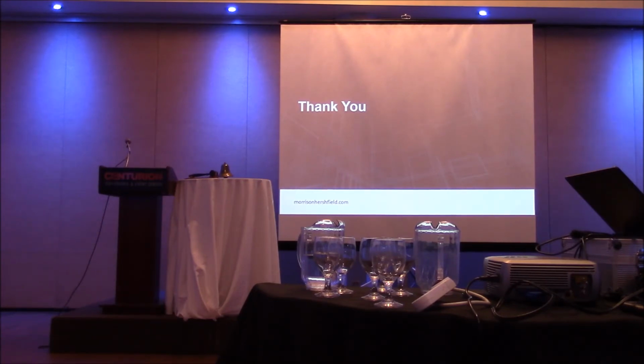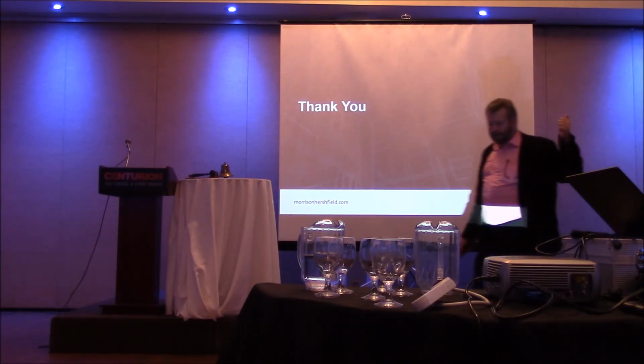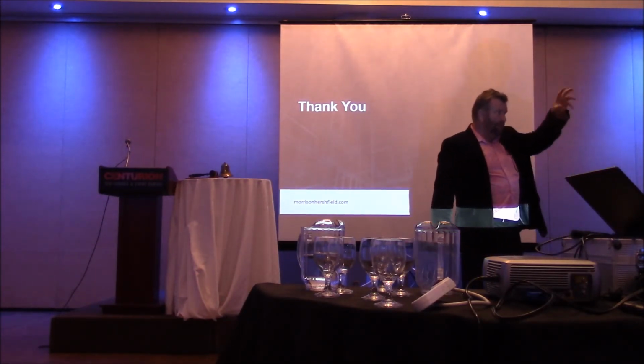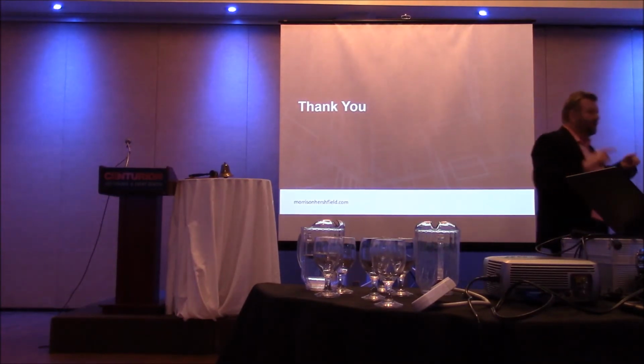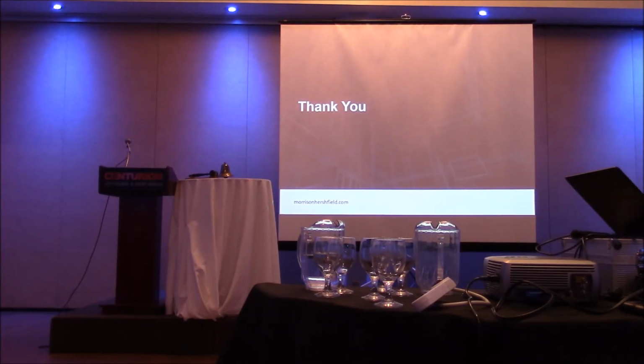So actually that's a really good question. This is that whole single phase versus three phase thing. The three phase diagram I was showing you, there's actually 3 wires coming to it. But we can create what we call single phase 600 volts or single phase 208 volts. And it's just a case of an electrical guy like me, you specify a unit heater. You've probably specified unit heaters at 600 volts when they're like 5 kilowatts, right? And the information will come to me, and I love 600 volts, especially for things like unit heaters.